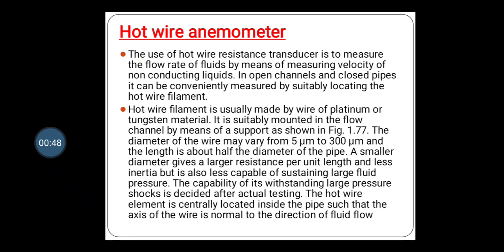Hot wire flow meter, that is a hot wire anemometer. This type is one of the thermal flow meters. Thermal flow meters are divided into heat transfer flow meters and hot wire flow meters. Thermal flow meters are suitable mostly for the measurement of unsteady flow of gases. They measure flow rate in terms of mass, which is a desired feature particularly in gas services.